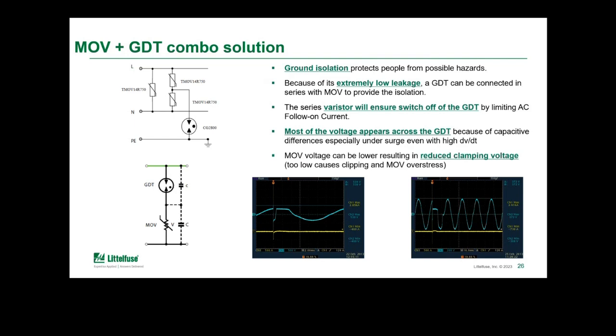Connected in series with an MOV, it will ensure that the GDT also shuts off once the transient event dissipates. The resistance of the MOV will limit the amount of follow-on current and ensure that the GDT will shut off. Since most of the voltage appears across the GDT due to the capacitive differences of the two devices, the standoff voltage of the GDT needs to be designed so that it is greater than the peak AC voltage of the AC mains waveform.